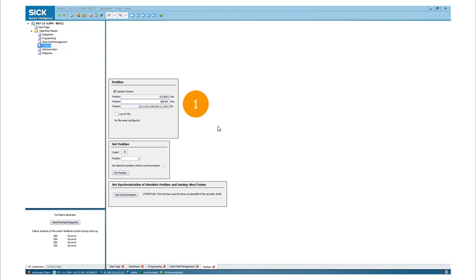The current position of the motor feedback system is shown in this tab. During commissioning of the servo motor, it is required to align the mechanical rotor position of the motor with the electrical position of the motor feedback system. This can be done in the set position window.